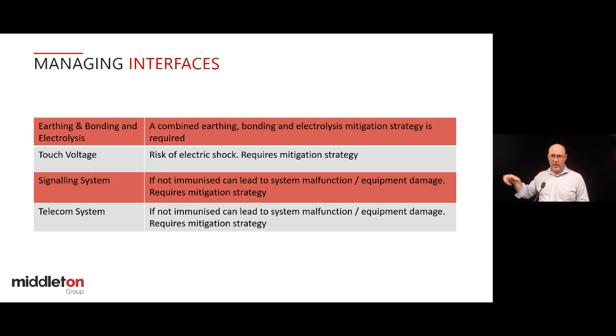And even though they're not on the railway, if you have an AC style track circuit on a DC railway, so 50 hertz, 60 hertz type track circuit, that will probably be interfered with by a 25 kV return current circuit. So you can't use that same technology on the AC railway. It also means that at the interface point, you can't probably use that technology on the DC railway. So you've got to change the signalling system, track circuits and other things to make sure they're compatible. They usually refer to that as immunisation of the DC railway against the AC issues.